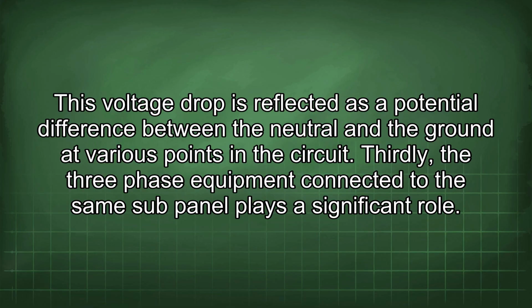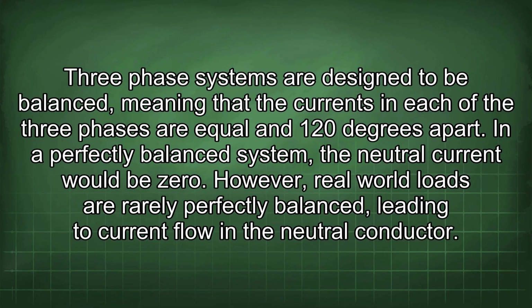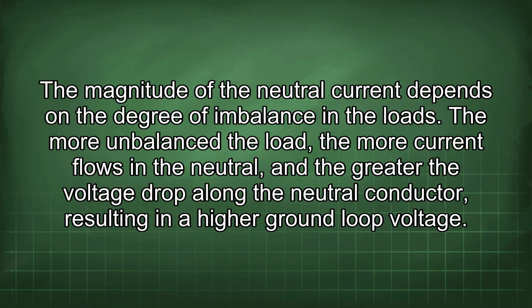Thirdly, the three-phase equipment connected to the same sub-panel plays a significant role. Three-phase systems are designed to be balanced, meaning that the currents in each of the three phases are equal and 120 degrees apart. In a perfectly balanced system, the neutral current would be zero. However, real-world loads are rarely perfectly balanced, leading to current flow in the neutral conductor. The magnitude of the neutral current depends on the degree of imbalance in the loads. The more unbalanced the load, the more current flows in the neutral, and the greater the voltage drop along the neutral conductor, resulting in a higher ground loop voltage.